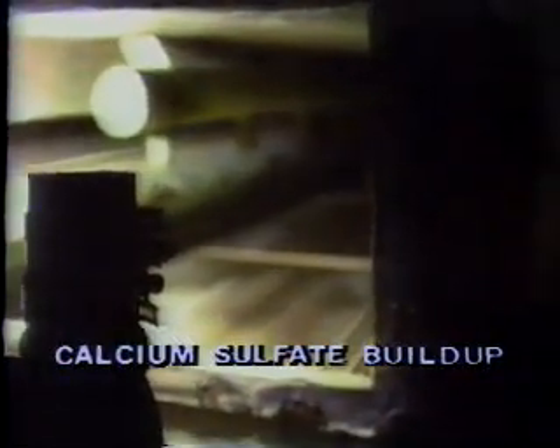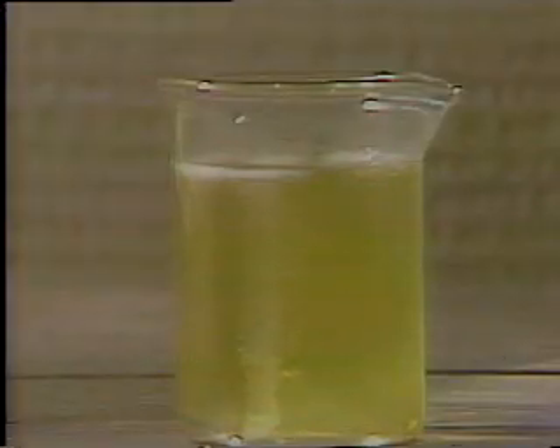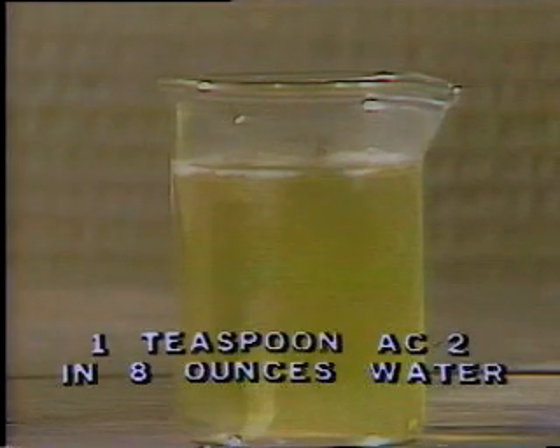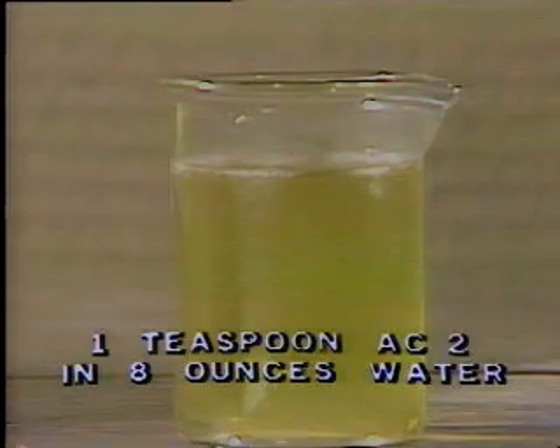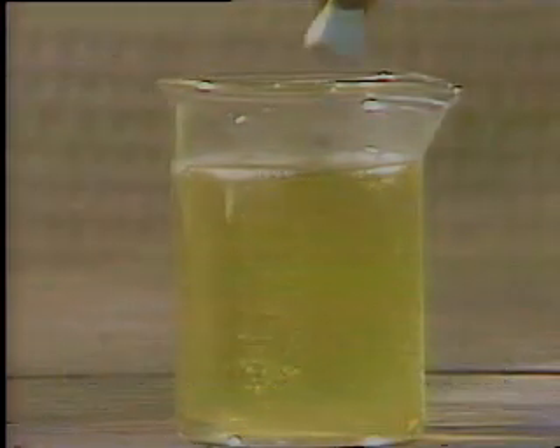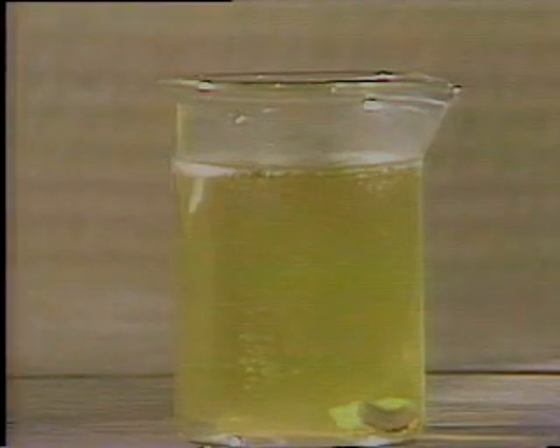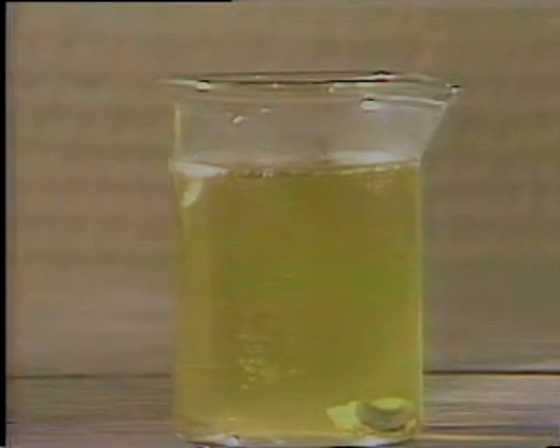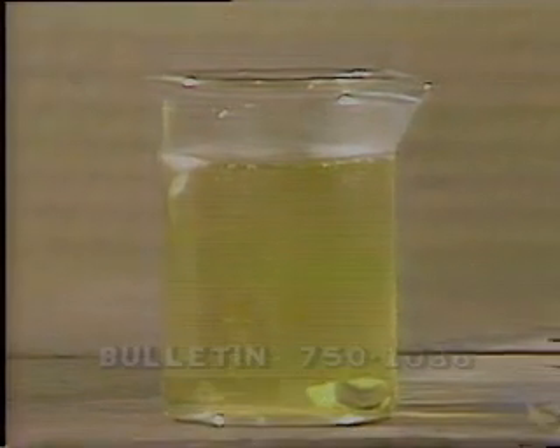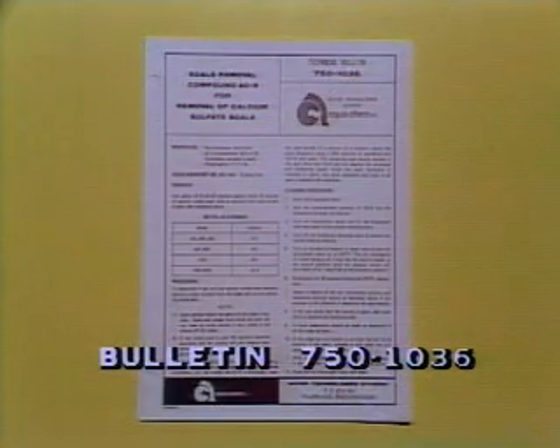Okay, good. Here's another problem. If you see scale buildup on your tube bundle and neither acid slugging nor acid cleaning seems to clean it off, you might be experiencing a buildup of calcium sulfate scale. Take a sample of the scale from the tube bundles. Mix a strong solution of AC2, about 1 teaspoon in 8 ounces of water. Drop the sample in. If it doesn't dissolve, it's almost sure to be calcium sulfate, and you'll need to get some AC8. The information for using AC8 can be found in Bulletin 750-1036 in your Aquachem manual.